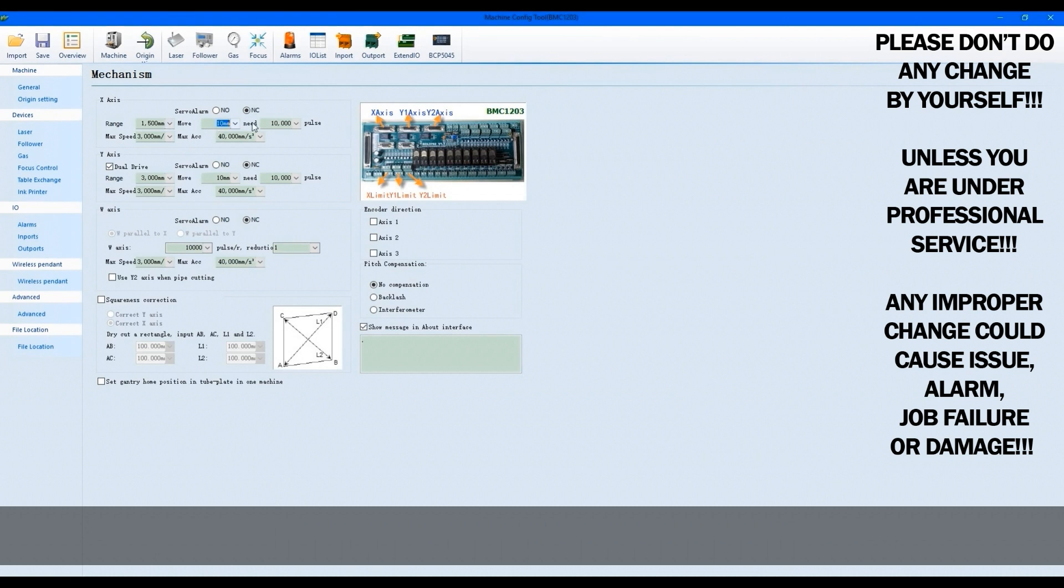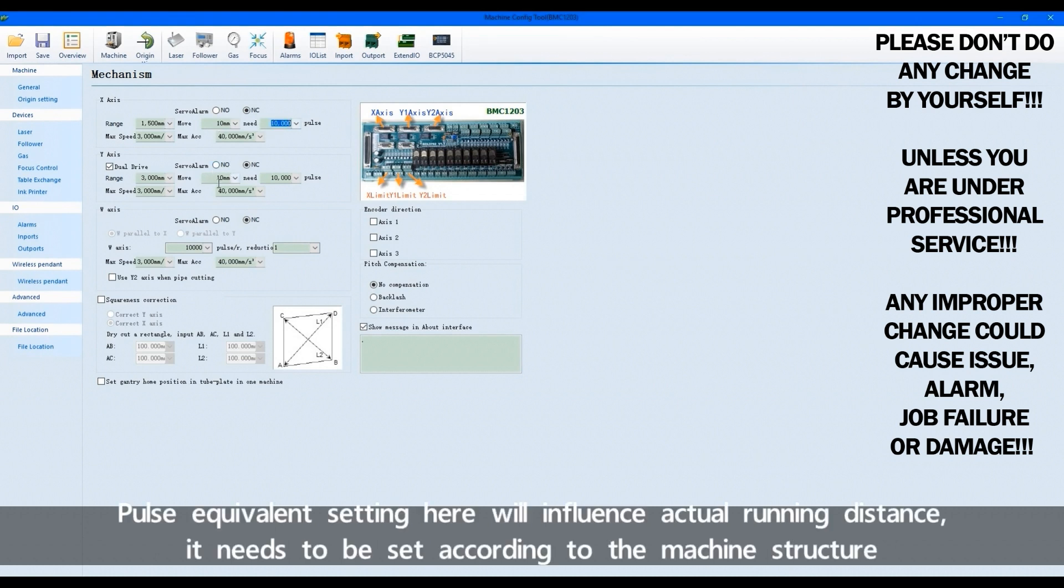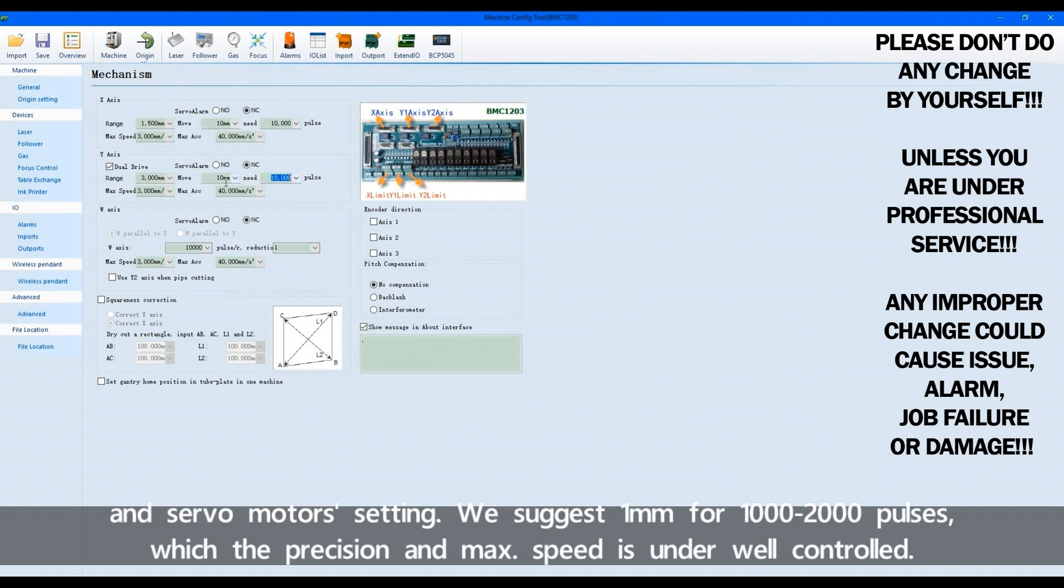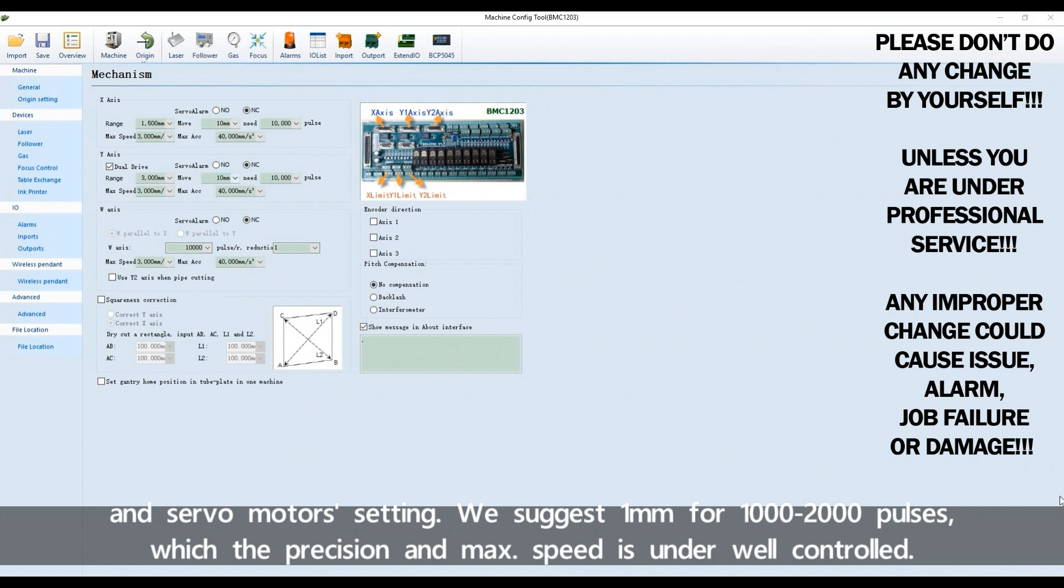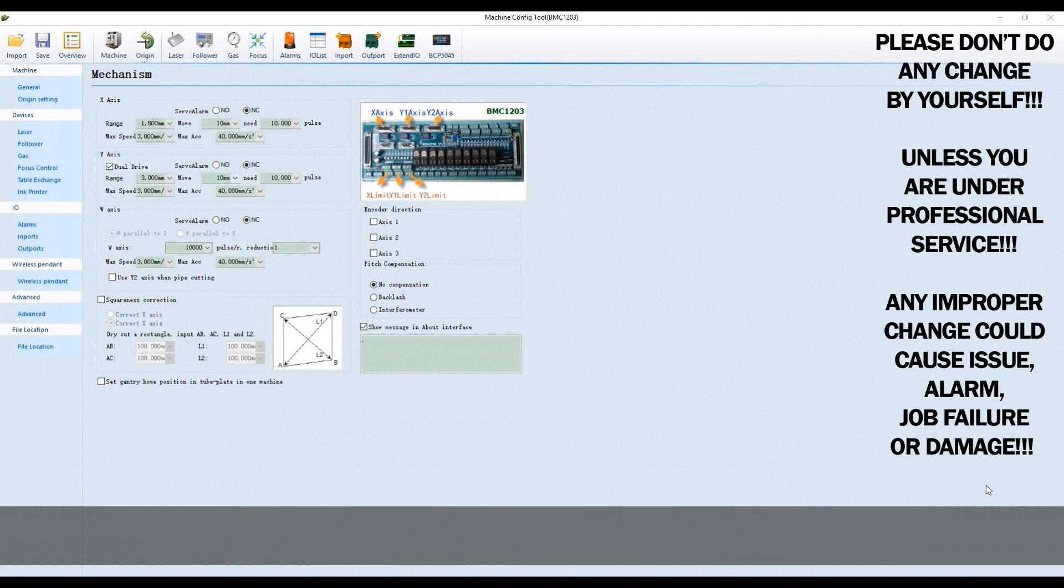Pulse equivalent setting here will influence actual running distance. It needs to be set according to the machine structure and servo motor settings. We suggest 1 millimeter for 1000 to 2000 pulses, which the precision and max speed is under well controlled.